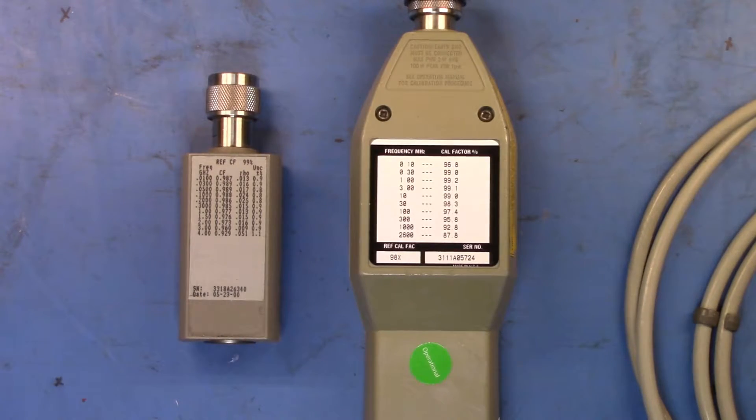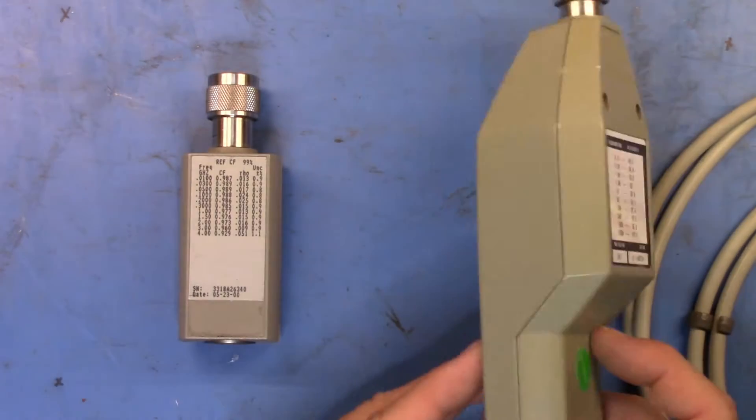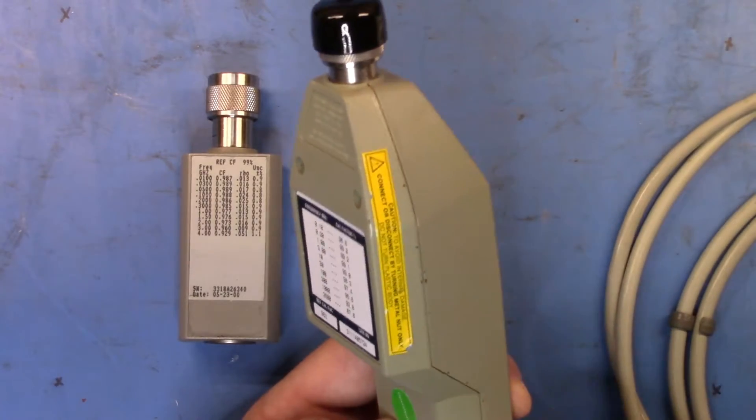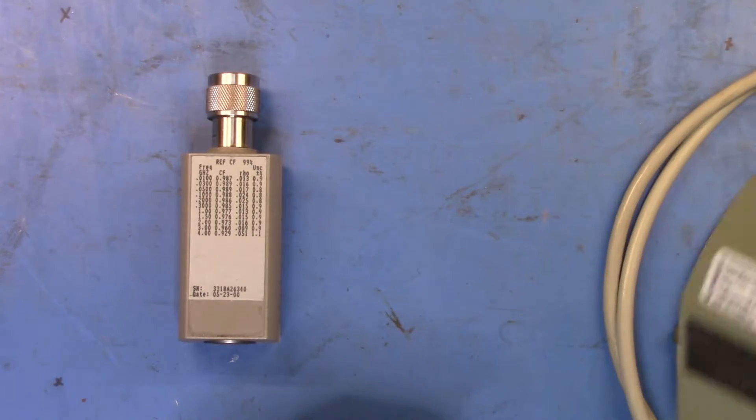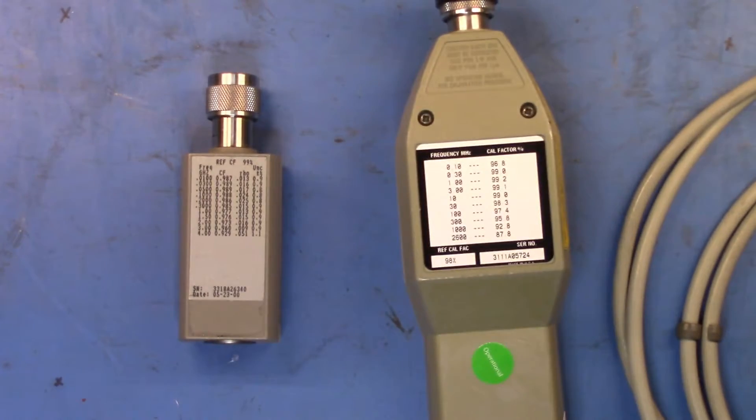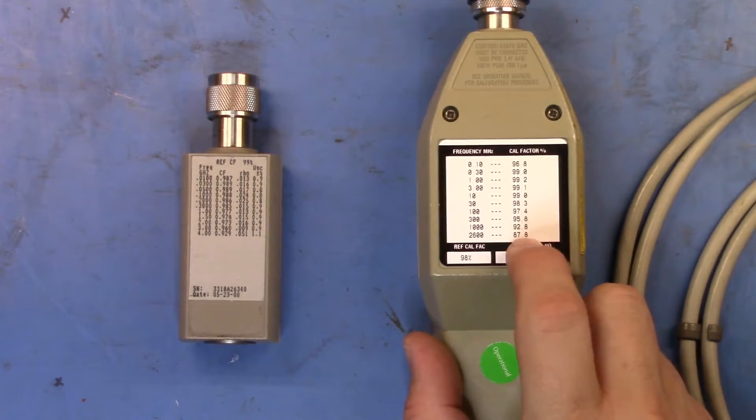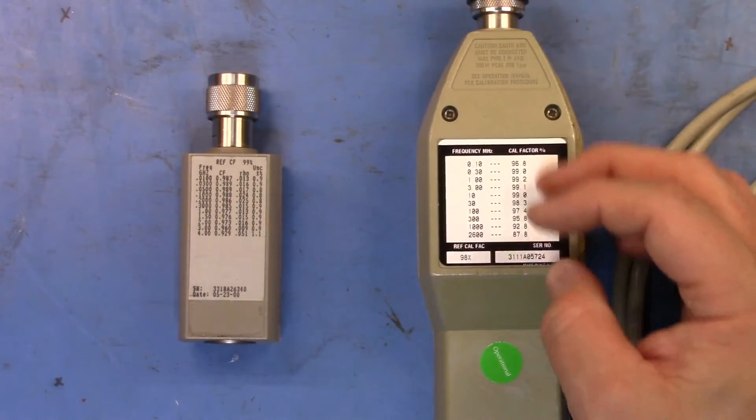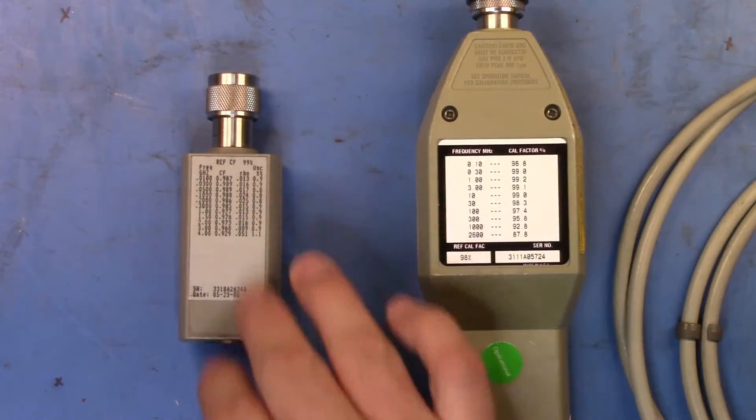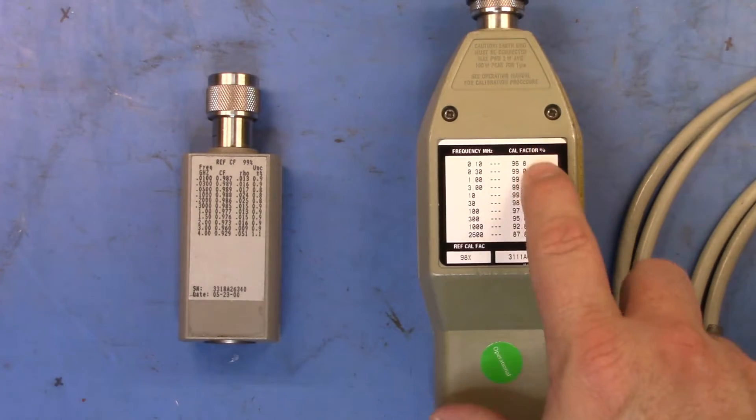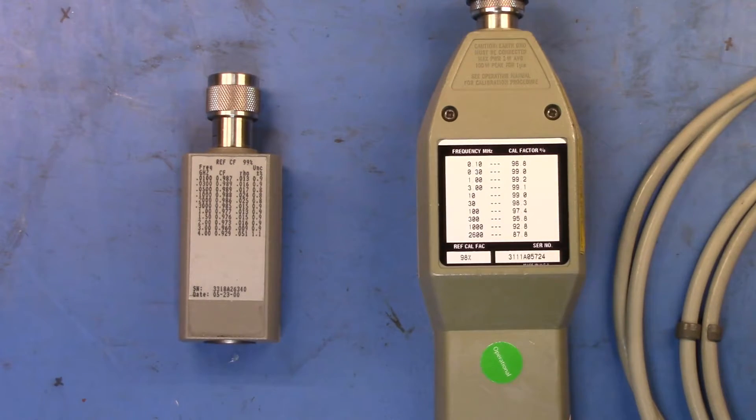That's it. You can see we have a nice little Keysight labels on it now that are locking it together. I'm going to be able to use that to get everything back into line. Now I may not calibrate this every year because these sensors, once they sort of warm in, don't really vary very much over the years, so it may not make a lot of sense for me to send it out again.